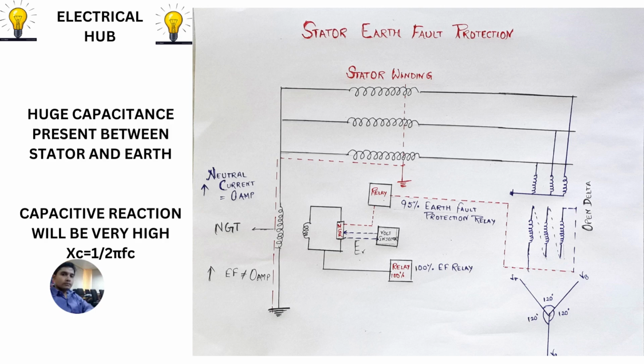But what will happen when there is a fault? When there is a fault, it means the insulation will break. So the capacitive reactance between the stator winding and the earth will become weaker, and a resistive current will flow through the NGT. The same current will also flow through the secondary winding and the NGR. So, as voltage is present and current is coming through the resistive path, the resistance will be sensed by the relay.